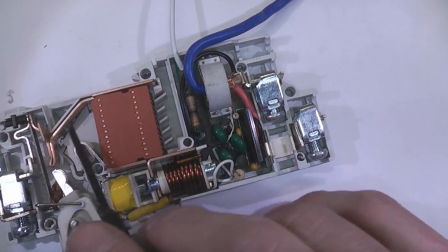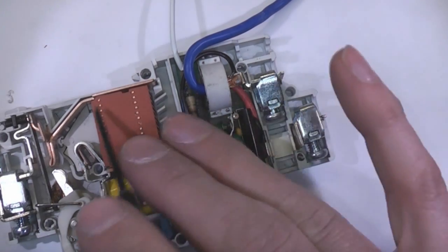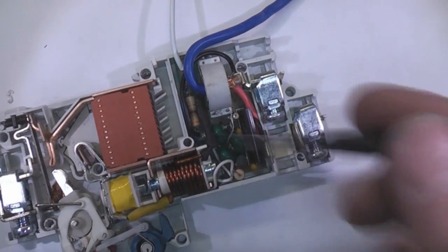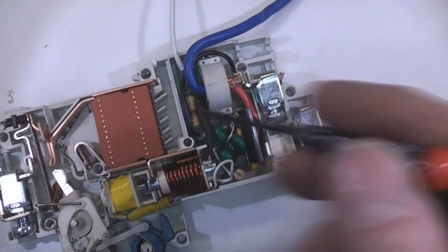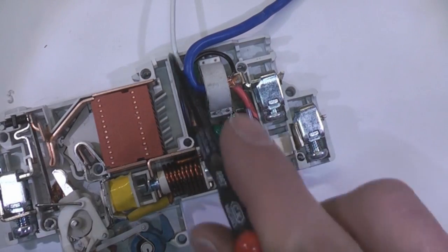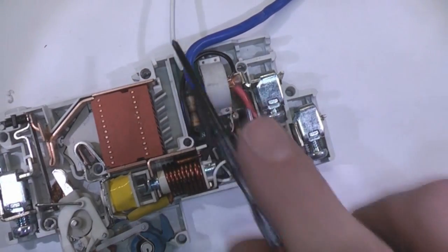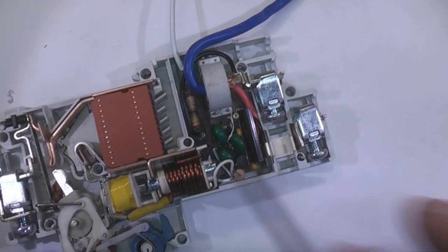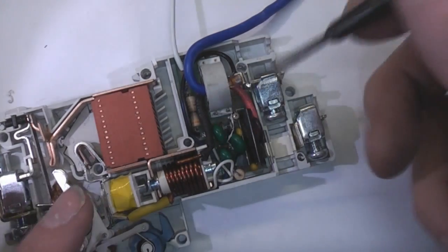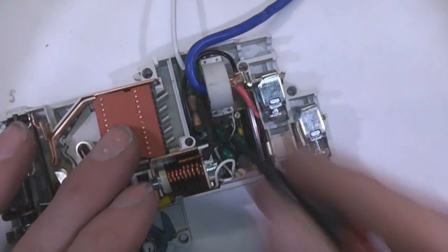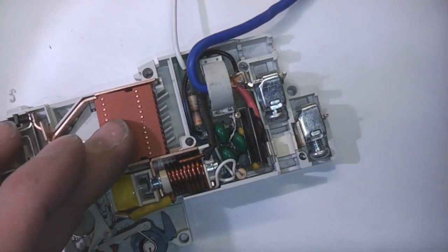So what happens is, if this does go into a really bad arc flash situation, again we're talking about this sort of 10,000 amp rating, that energy is pushed backwards first, so that if some guy's working on the switchboard, the energy has a nice easy way out rather than forcing its way out the front.